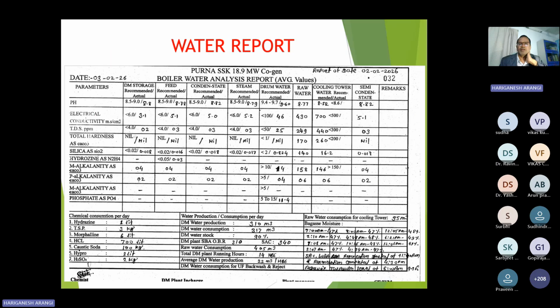This is one sample report of how the water quality is monitored in any plant. If you take the DM storage tank: pH, conductivity, TDS, hardness, silica, hydrazine, alkalinity, and phosphate, how they are monitoring. The DM storage tank, where it is generated, then the feed water, condensate system, steam, boiler, all the several places they will monitor and test, regularly, once in 4 hours or once in 8 hours. If there is any variation, they have to improve the water quality by dosing some chemicals.